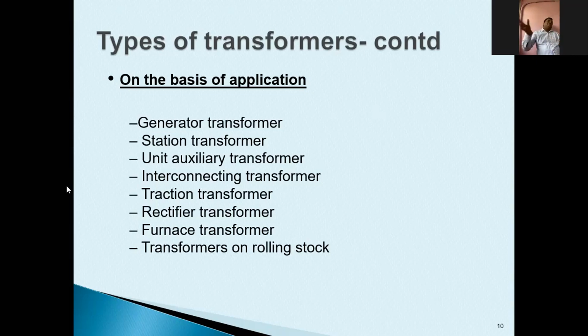Now this station transformer will have power connections from two or more substations to keep this station load intact. Even if your power plant is under shutdown, your station should be charged. All auxiliary load should be available. The electricity for auxiliary load should be available. So in this way, transformers are distinguished according to their applications, and they are named differently.